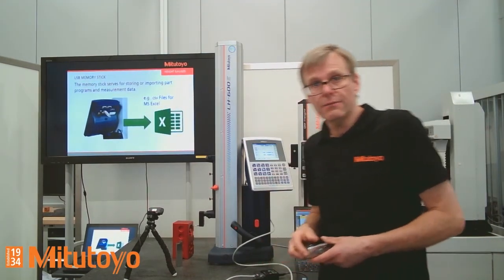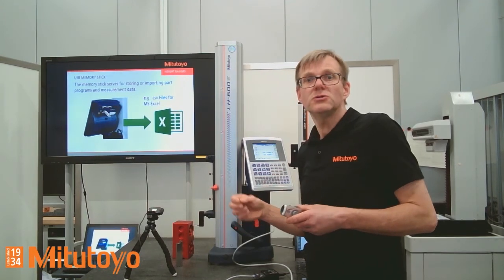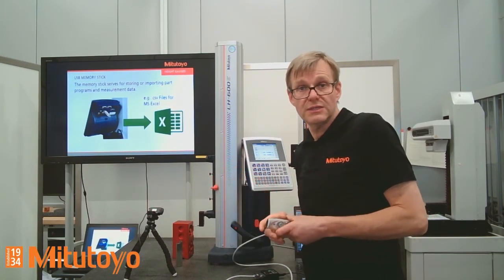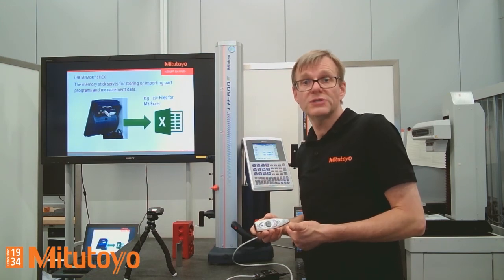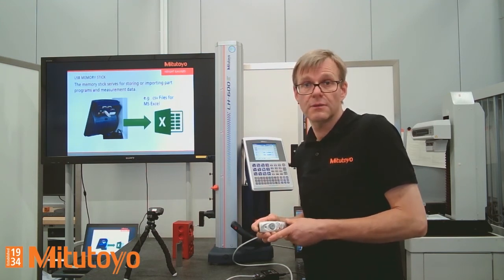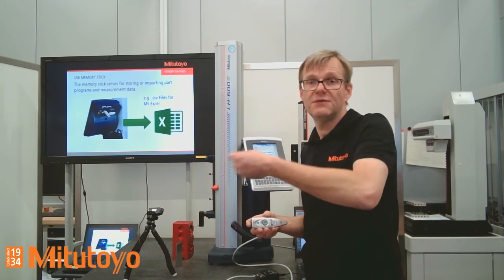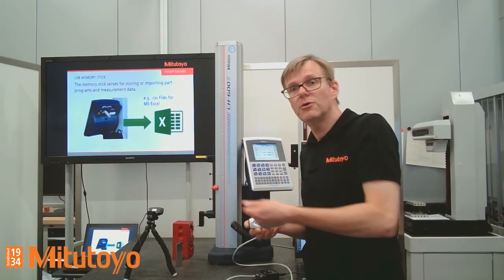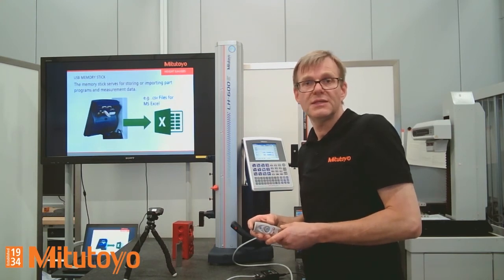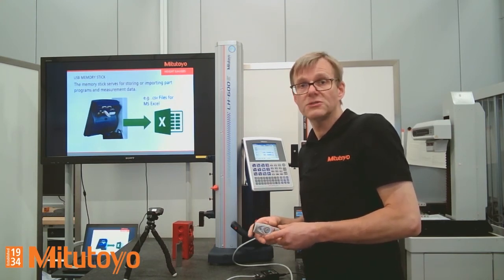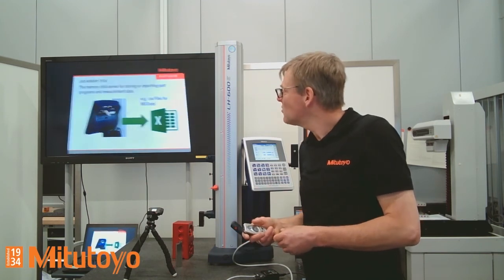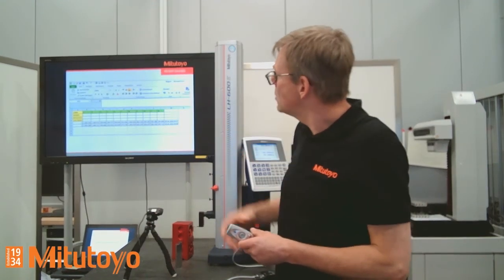Additionally, as I already explained, you can use an ordinary USB stick to save part programs or to save measured results. Later on, you can go from the production line to the PC, put the USB stick into the PC, and send the data via CSV format to Excel, for example. So this is a typical example here. This is a result of the execution of two part programs, and after this, I sent this very easily to Excel.